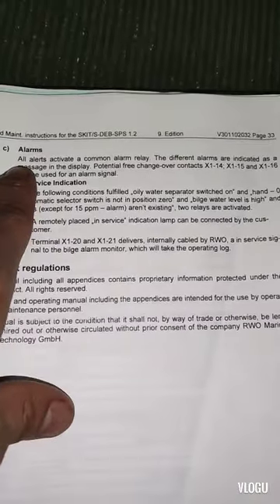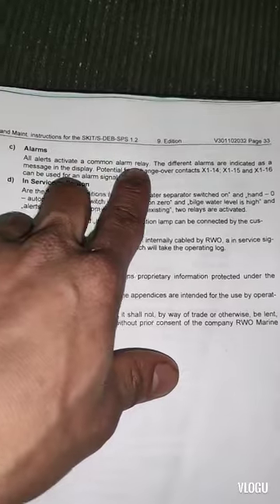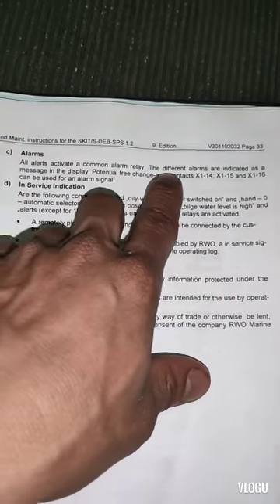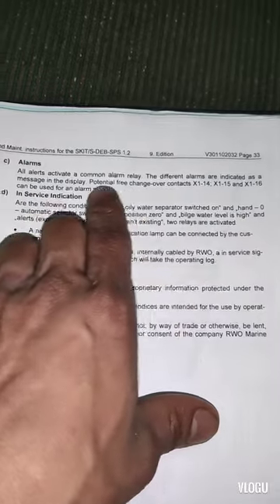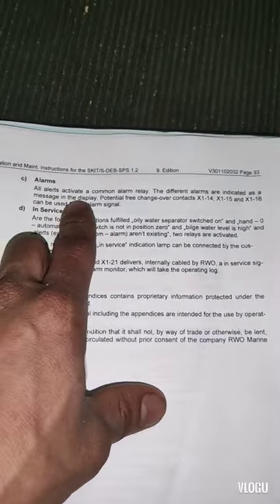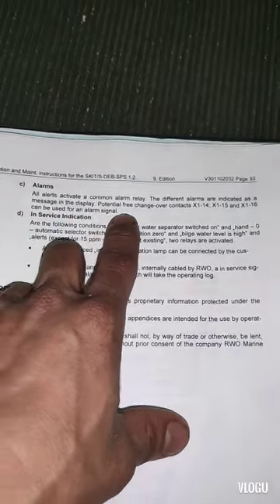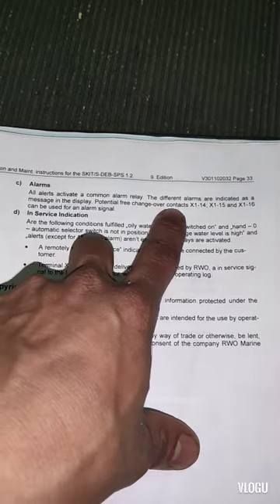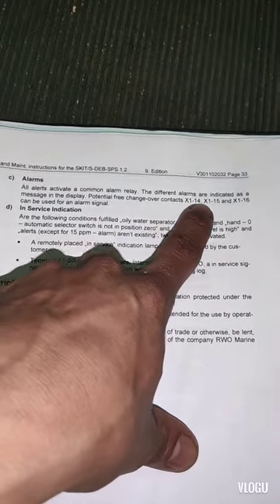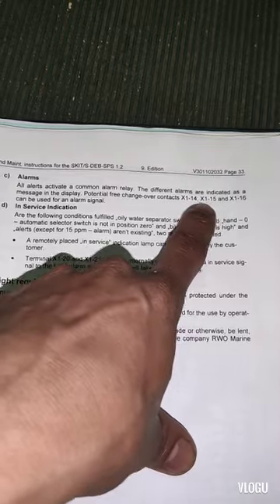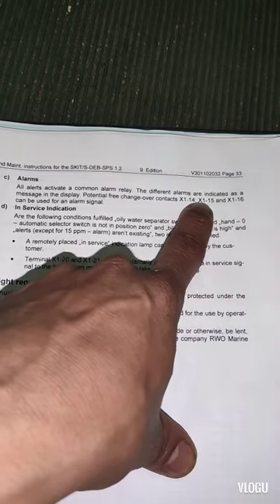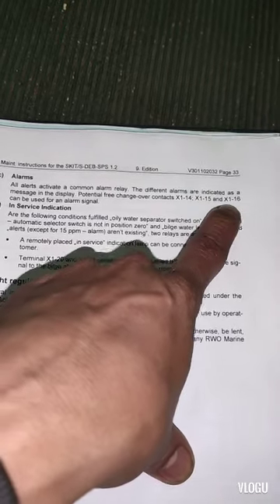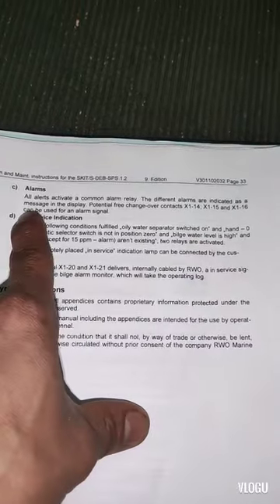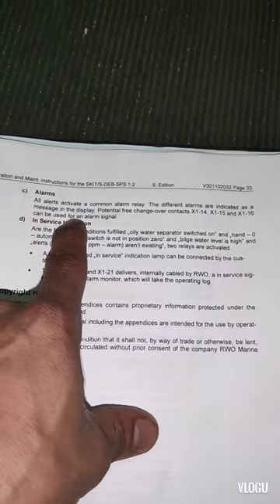Alarms. All alerts activate a common alarm relay. The different alarms are indicated as a message in the display. Potential-free changeover contacts X1 14, X1 15, and 16. So that's the contact that we need to check. It can be used for an alarm signal.